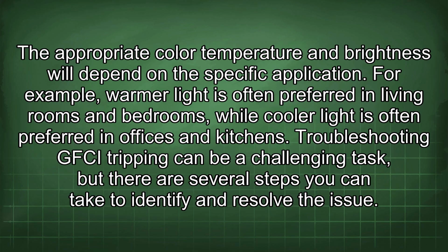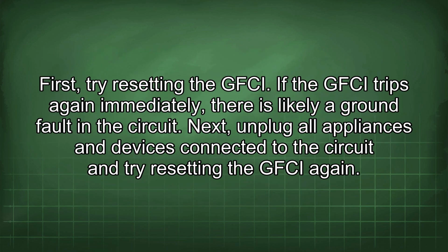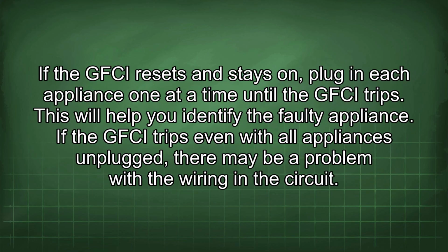Troubleshooting GFCI tripping can be a challenging task, but there are several steps you can take to identify and resolve the issue. First, try resetting the GFCI. If the GFCI trips again immediately, there is likely a ground fault in the circuit. Next, unplug all appliances and devices connected to the circuit and try resetting the GFCI again. If the GFCI resets and stays on, plug in each appliance one at a time until the GFCI trips. This will help you identify the faulty appliance.